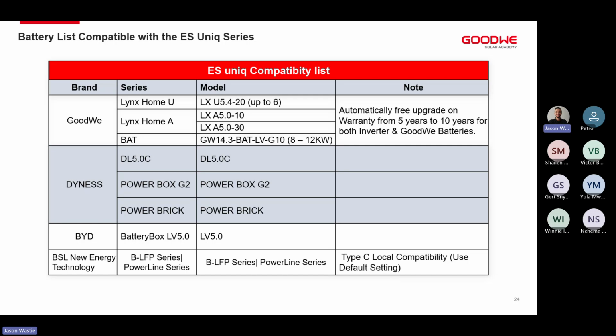So for example, the Dyness DL 5.0C battery, we gave Dyness an inverter, Dyness gave us a battery, and their protocol, we gave them ours, and we made sure we matched protocol line by line. When doing that, so we have international compatibility, then anywhere in the world, we'll be able to use this Dyness battery. The second way we do battery compatibility is with our type C or local compatibility. And this is where we have a default protocol on GoodWe side. We have an LV default protocol.